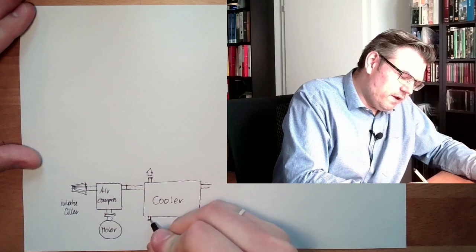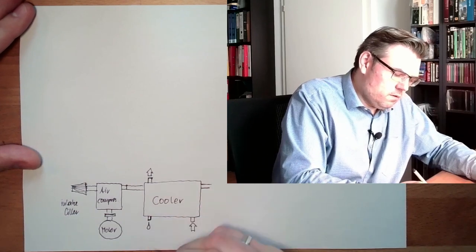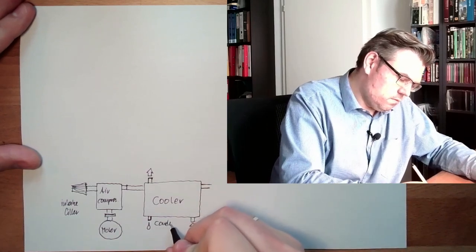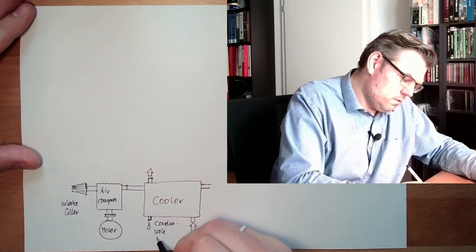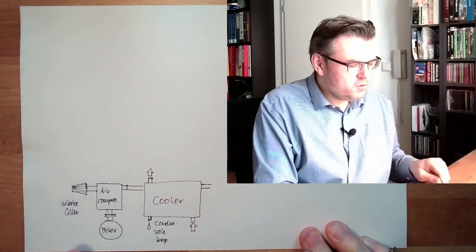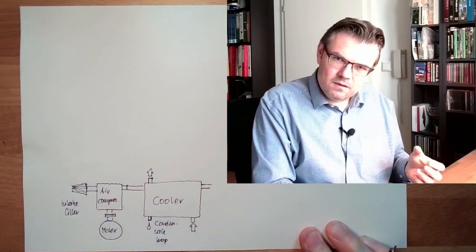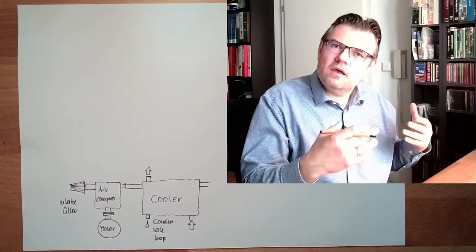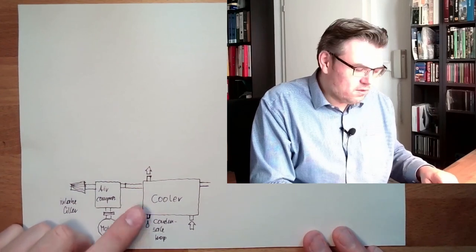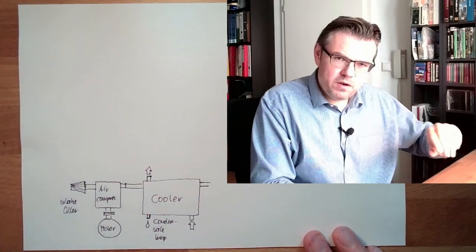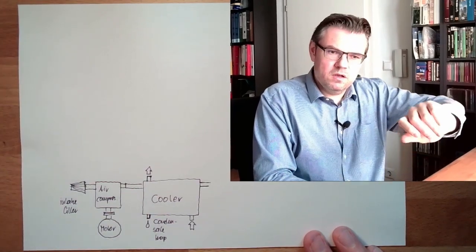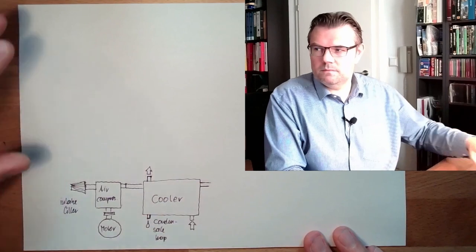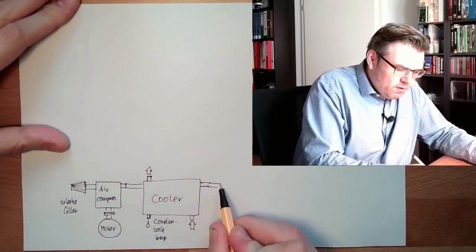Mandatory at a cooler is something like this, a drop, a condensate trap. Usually if we cool air, it's condensating. So the moisture of the air is getting again to water, and this water needs to be taken out somehow. So this is the condensate trap. Simply, the most simple one is you open it and close it with some sort of ball valve. Okay? Cooler.